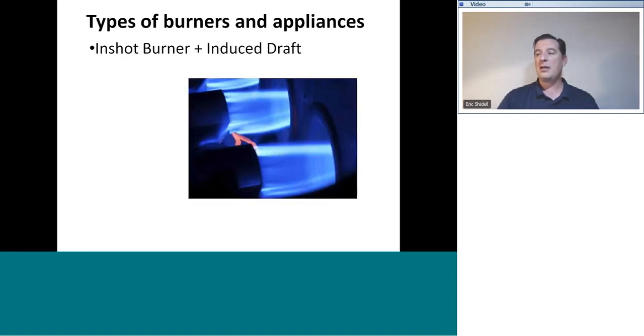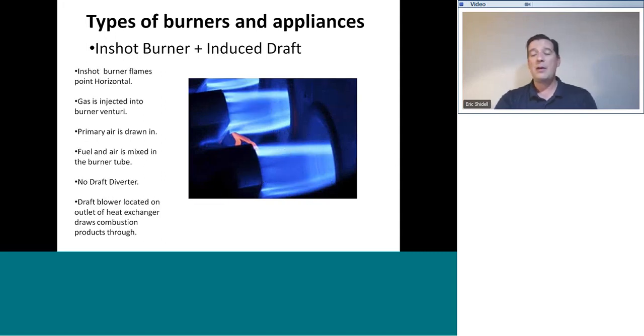Next burner we're going to talk about is the in-shot burner with induced draft. In-shot burners are common in your 80% and 90% AFUE gas furnaces. In-shot burner flames point horizontally. They don't follow the rule of going up, they go sideways.